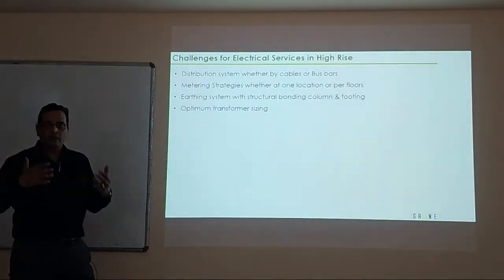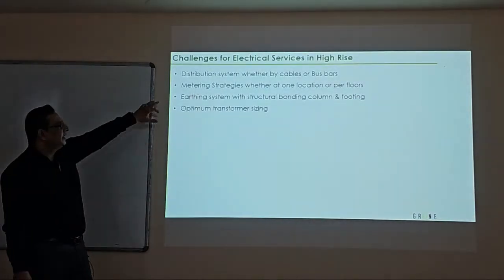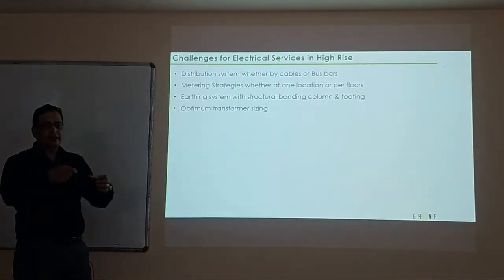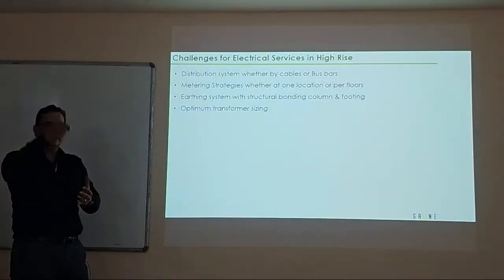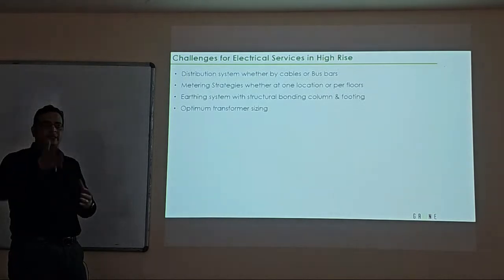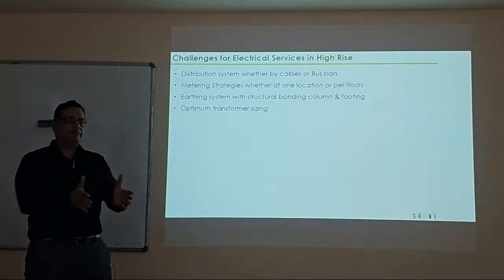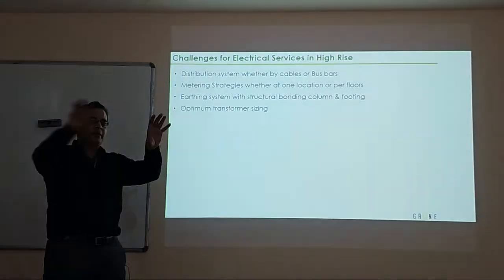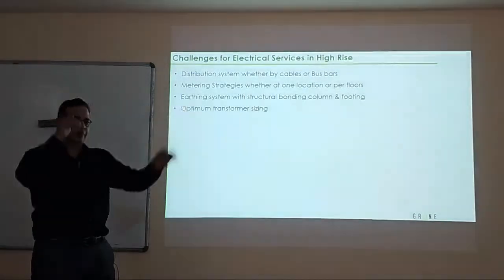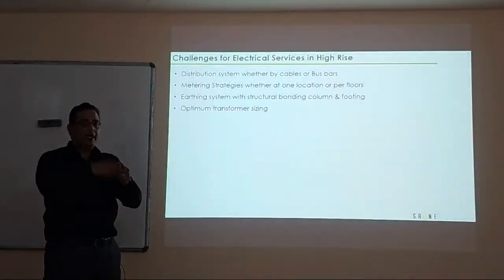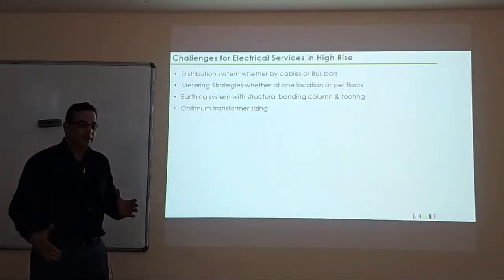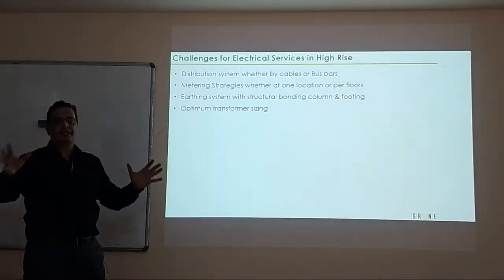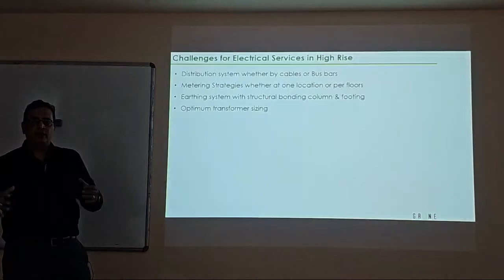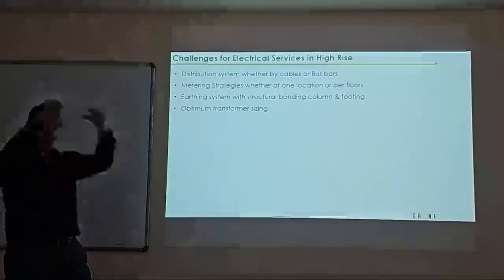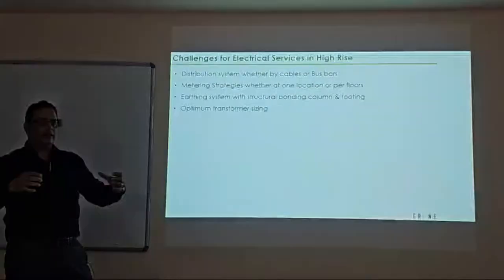Now when you go to a high-rise building, because high-rise is always the biggest challenge, we need to look at whether the building is serviced by cables or by a system called a bus bar. So we give power in bus bars, and from the bus bar we tap into every floor and then the power goes to the relay system. If you do a cable per flat, you can imagine the number of cables that will come in a building of 300, 400 flats. That many cables will travel from bottom to top. The more the number, the greater the fire risk in a building.